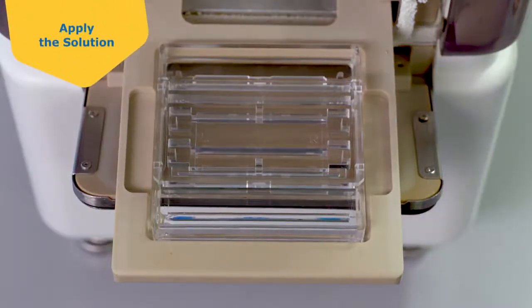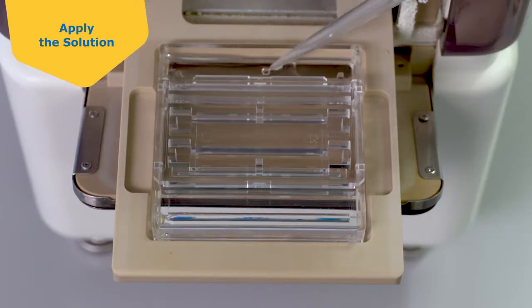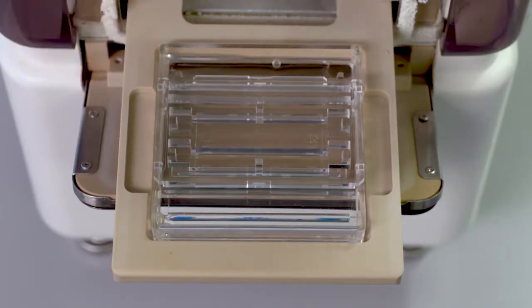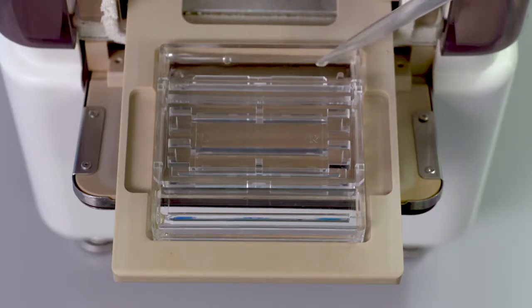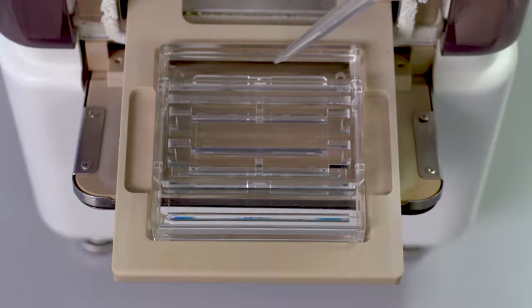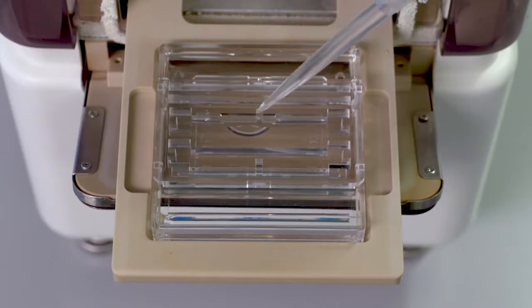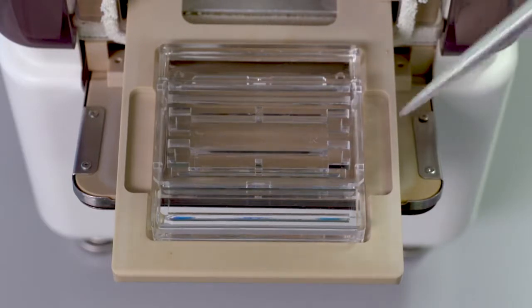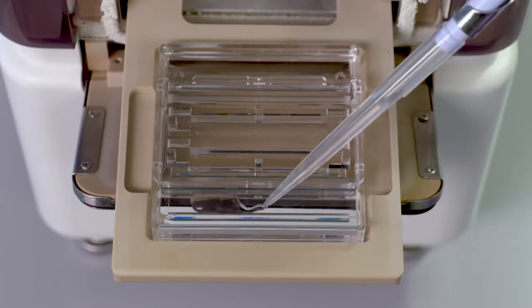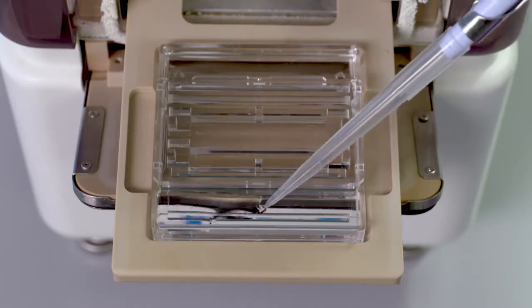Load reagents into the Solution Chip Plus. First, add cathode buffer to the groove at the cathode side of the PAGE chip. Then apply DI water to the hole in the center of the chip. Next, apply anode buffer to the anode side of the PAGE chip.